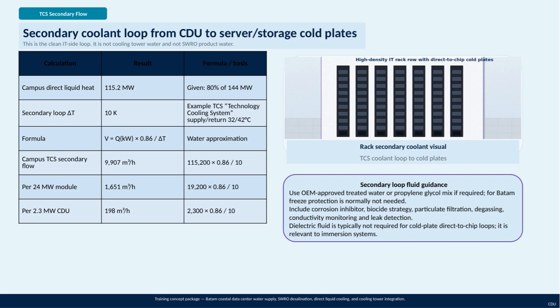Visually, the rack secondary coolant loop channels this fluid directly to the cold plates, providing efficient heat transfer. When it comes to fluid selection, the loop uses OEM-approved treated water or a propylene glycol mixture if freeze protection is necessary. At the Batam site, freeze protection is generally not required. Additionally, the fluid needs to have corrosion inhibitors, biocide strategies, filtration to remove particulates, degassing, conductivity monitoring, and leak detection.